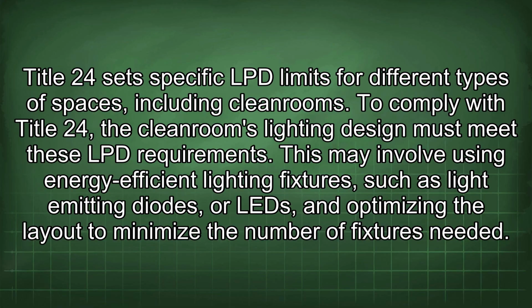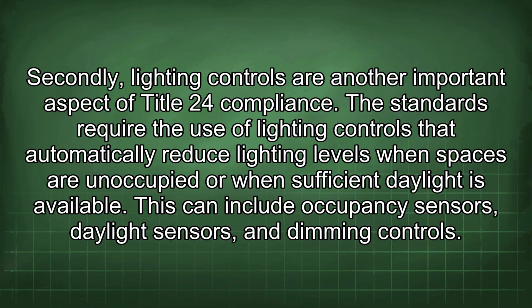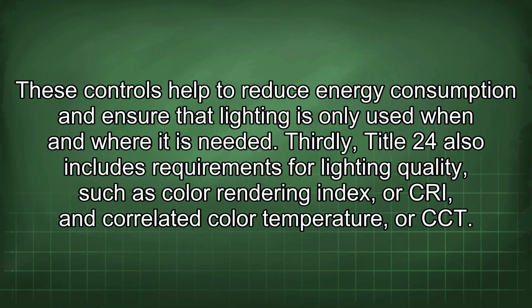This may involve using energy-efficient lighting fixtures such as light-emitting diodes, or LEDs, and optimizing the layout to minimize the number of fixtures needed. Secondly, lighting controls are another important aspect of Title 24 compliance. The standards require the use of lighting controls that automatically reduce lighting levels when spaces are unoccupied or when sufficient daylight is available. This can include occupancy sensors, daylight sensors, and dimming controls. These controls help to reduce energy consumption and ensure that lighting is only used when and where it is needed.